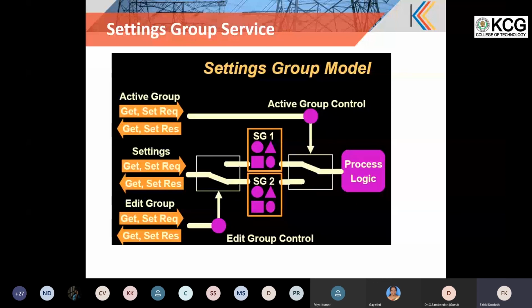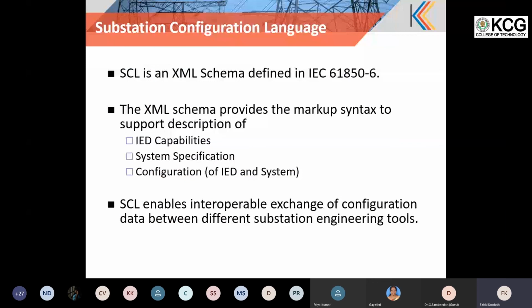Then moving on to the substation configuration language. I have already explained this in the earlier slide. This is defined in 61850-6. This is an XML schema for representation of IED capability and exchange scenario. The configuration language is defined, containing logical nodes, communication models, and data elements; everything is defined.